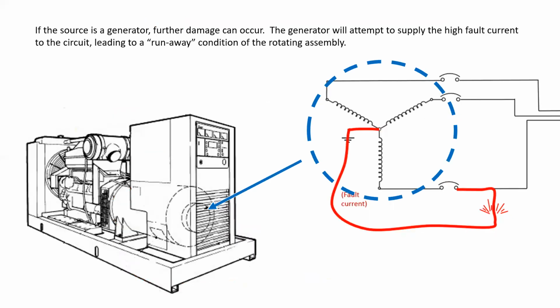In other situations, if the source is actually a generator, further damage can occur, and that's because the generator will attempt to supply the high fault current to the circuit, leading to a runaway condition of the rotating assembly, and this can cause damage to the generator.